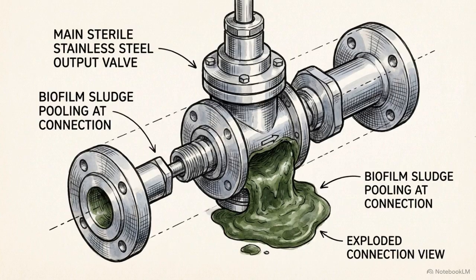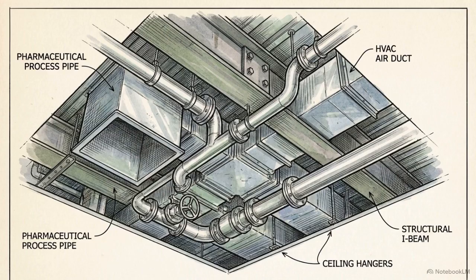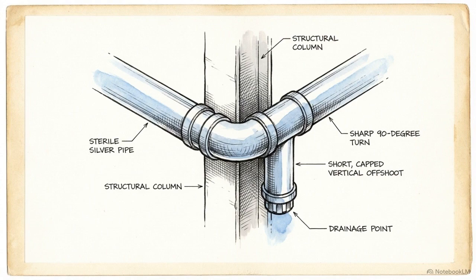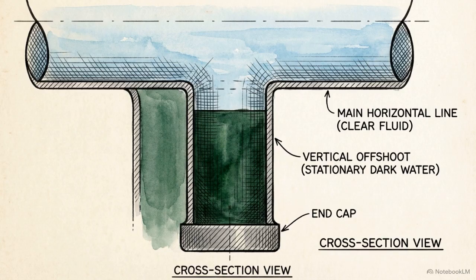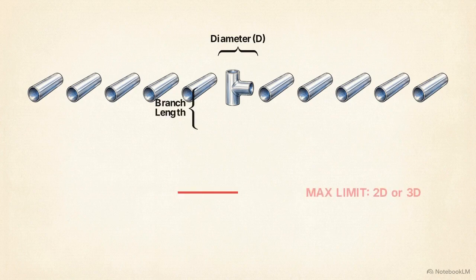Maintaining a consistent slope is a challenge in crowded utility plenums, where pipes must navigate around HVAC ducts and structural beams. When these obstacles force a change in the pipe's path, there is a high risk of creating dead legs, sections of the pipe where water remains trapped. We manage this through the 2D or 3D rule. The length of any stagnant branch must not exceed 2 or 3 times its own diameter, as seen here.